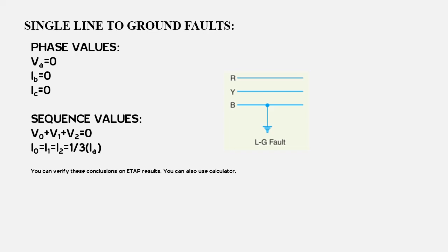If we talk about sequence values, the vector sum of sequence components of the voltages is going to be zero in a single line to ground fault. And in a single line to ground fault, the sequence current components are equal, and they are equal to one third of the fault current.